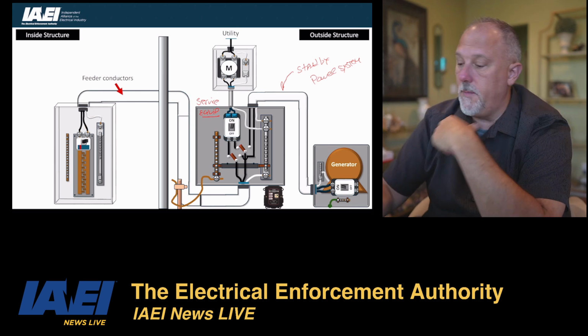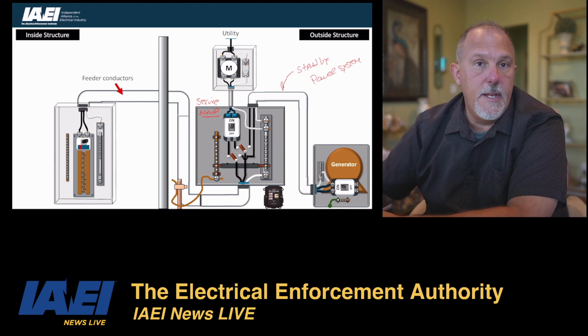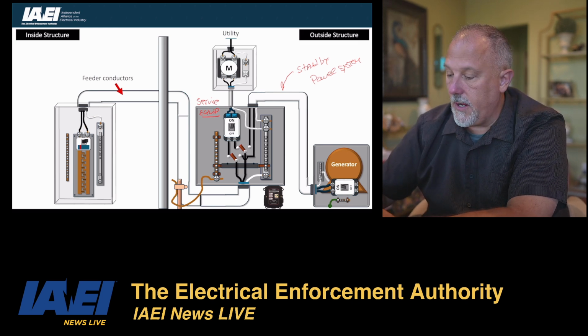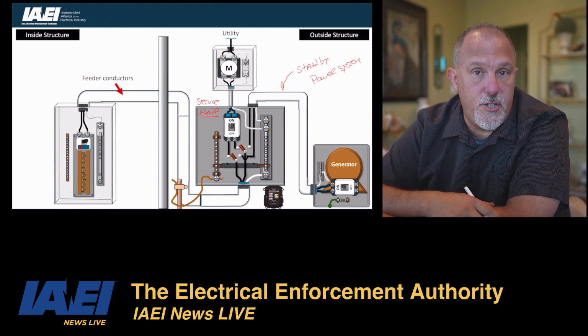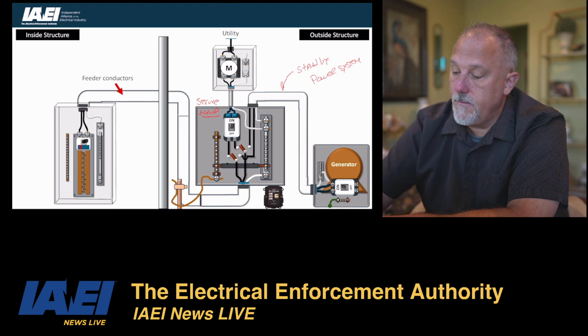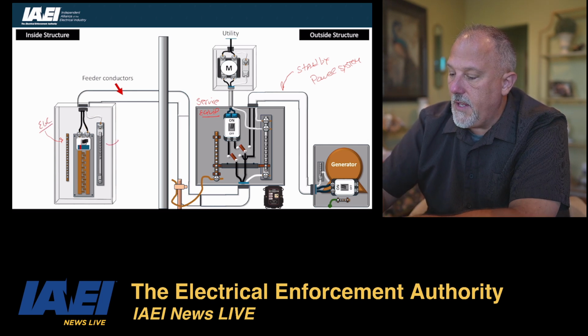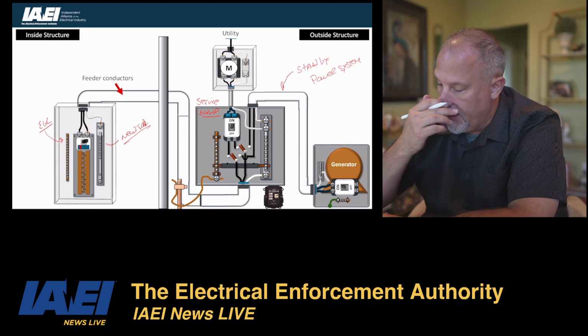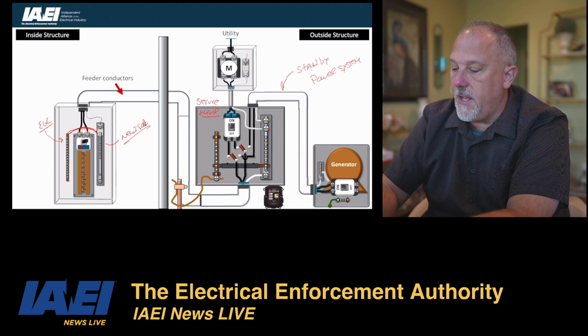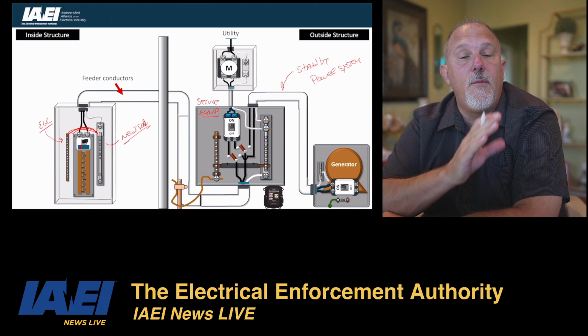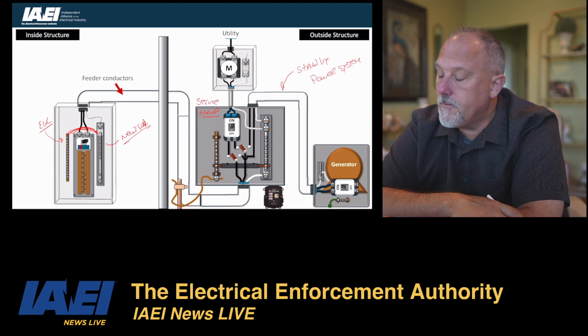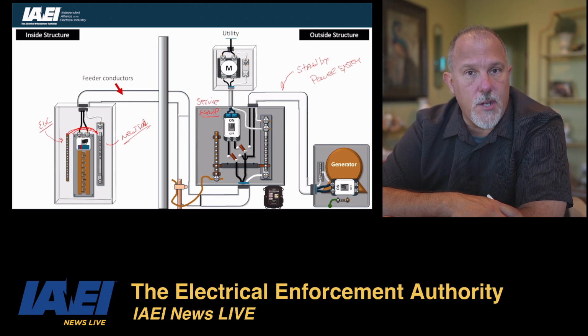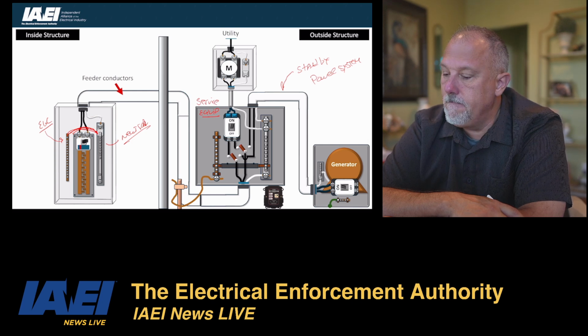Now, if this is service equipment, that means all of the grounding and bonding had to be done in that enclosure. And then that means that nothing downstream can bond the equipment grounding conductor, the EGC bar, with the neutral, or the grounded conductor. So that bonding strap that is in between these two has to be removed. And what we walked away with was that when you're installing this in an existing installation, that bonding strap would have to be removed.